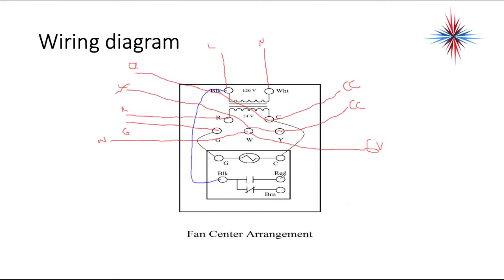The red goes to the cooling speed on the fan. So on your fan motor, this would probably go to high because our cooling speed is high. The brown wire, which is the normally closed, goes to my combo fan limit switch. Or whatever controls the fan on the heating side.